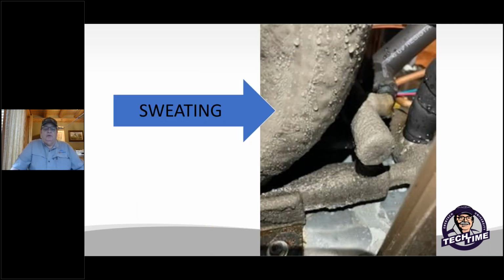This is one of the pictures the technician sent me. As you can see, that's our coax, and you can see the water droplets and drips on it. This is what filled up the water pan and eventually ran out onto the floor. So this is sometimes mistaken as an internal water leak by consumers seeing this on their floor.